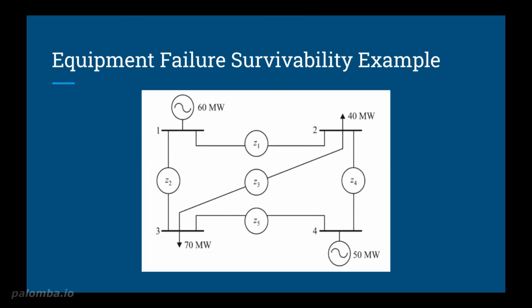Under the traditional approach, this could potentially cause a differential scheme to take an electrical bus offline. But we're going to suppose that this bus supplies critical loads and must be kept energized at all times. So the simulation can be easily accomplished by changing one of the real power measurements to be 0 and rerunning the simulation. And under the scheme that uses state estimation, as we have just discussed, the bus would survive because the bad data associated with the disconnected CT would be discarded, and the protective relay would recognize a more accurate state of the true current in a line. And similar results can be evaluated for saturated CTs.